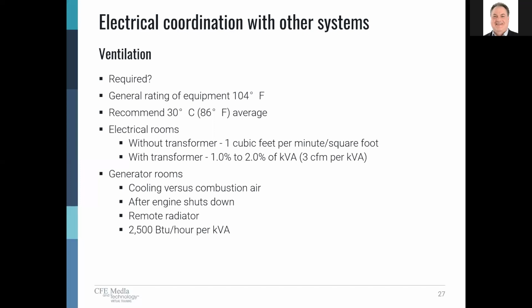We like to recommend that you put that at about 86 degrees Fahrenheit average for worst case design day conditions or less. So when you're talking with your mechanical engineer, there are some rules of thumb you can use before you actually go get the actual heat rejection values from your equipment's vendor. If you've got a room without transformers in it, just gear, panels, those types of things, a general rule of thumb is to give your mechanical engineers 1 cubic foot per minute per square foot.